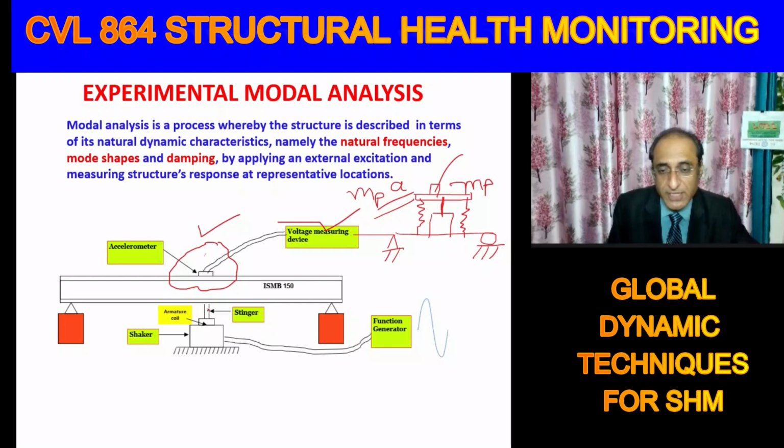Now here in this case, the stinger type, what we have to do is, in between the stinger and the structure, install an additional sensor, the force sensor.